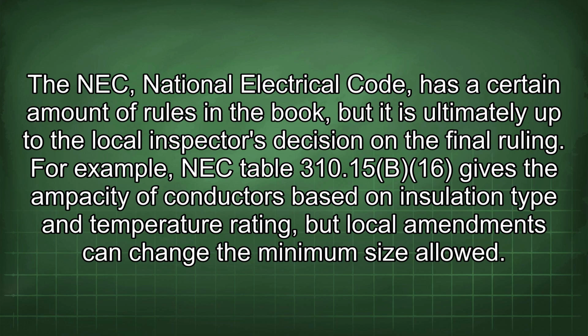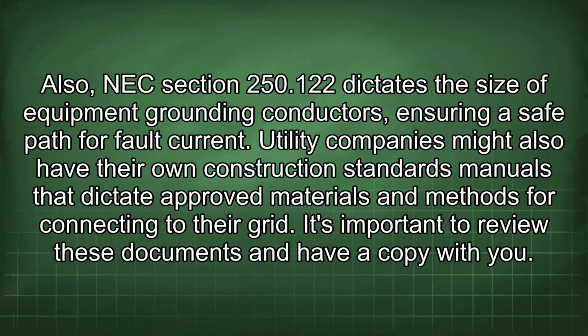For example, NEC Table 310.15(B)(16) gives the ampacity of conductors based on insulation type and temperature rating, but local amendments can change the minimum size allowed. Also, NEC Section 250.122 dictates the size of equipment grounding conductors, ensuring a safe path for fault current. Utility companies might also have their own construction standards manuals that dictate approved materials and methods for connecting to their grid. It's important to review these documents and have a copy with you.